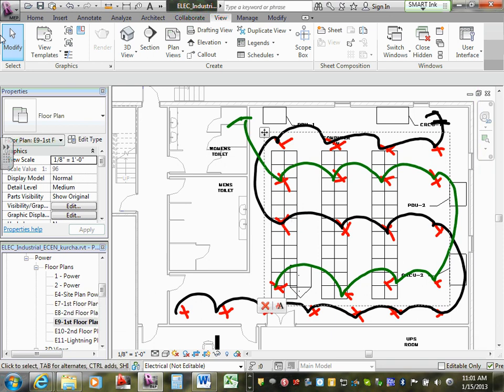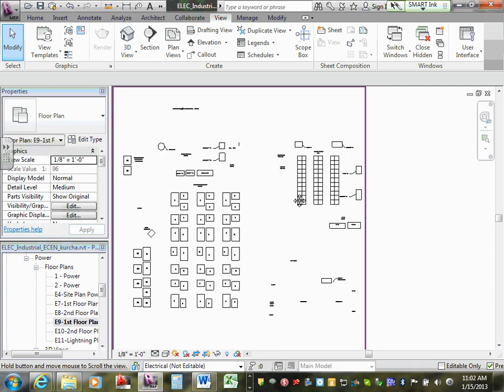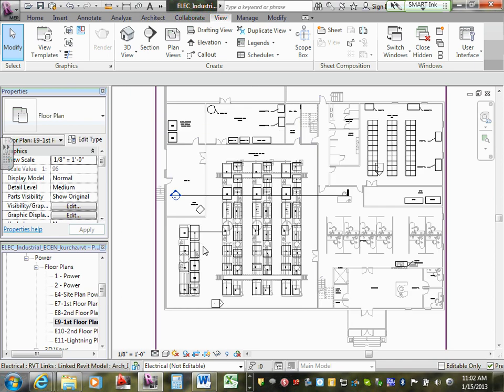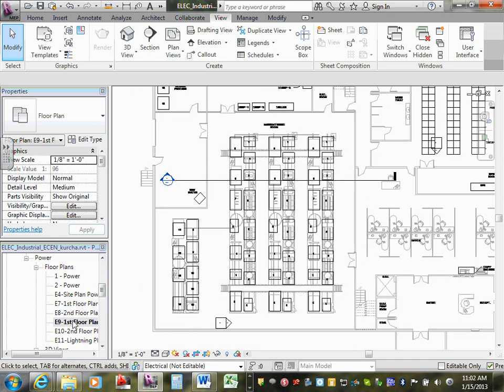Second floor. Oh, yeah, there's one thing. In the manufacturing area we specified what do you call these, beam smoke detectors. Yes, beam detectors. Just a few things about that. Beam detectors are pretty much exactly what they sound like. You got a transmitter on one side, a reflector on the other side. And just as the beam goes out, it creates a space 35 degrees on either side where you're looking. So it covers the majority of the area.